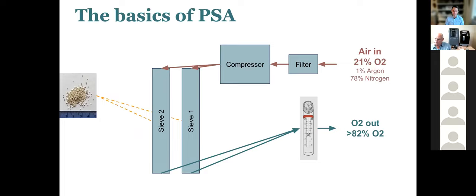As it enters the machine, the first thing that happens is it's filtered. A filter will try and take out any gross particulate matter, dust, things that can really damage the internal workings of these devices. In many of these devices, there's actually a series of filters, and we'll talk about those a little bit more. The next step is to compress that gas, bring it up to pressure, and drive it through these two sieve beds. You can think of the sieve beds as filters, and they're filled with the substance on the left. There are a couple of different ways that these can work, but here we show zeolite, a compound that works like a filter, but it basically filters out the nitrogen. You can think of it as working in that way.